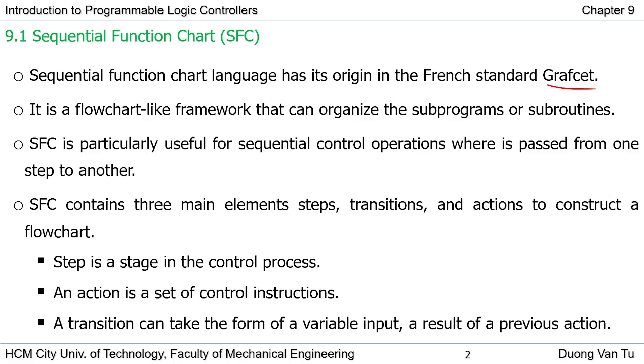This language is useful for sequential control operations, going one step to another step. For example, consider a mixer system: we can divide it into many steps. The first step is to fill material A and B, the second step is to turn on the mixer, and the third step is to open the valve to drain the mixture. For many applications, we can divide into many steps and use the SFC language to prepare the control program for the PLC.